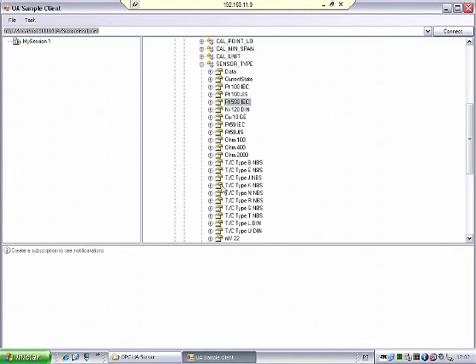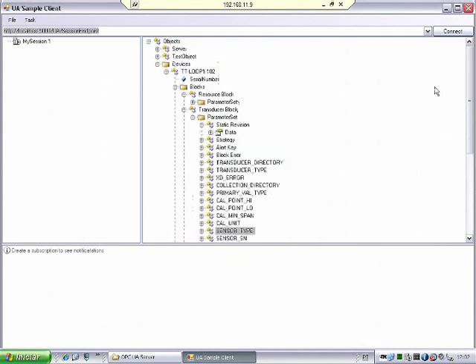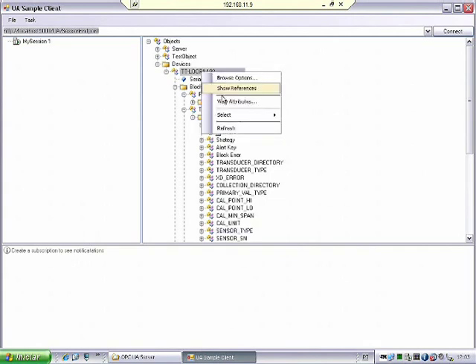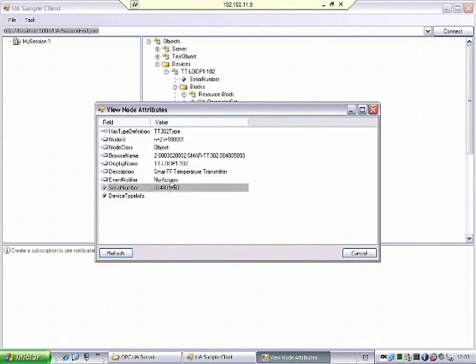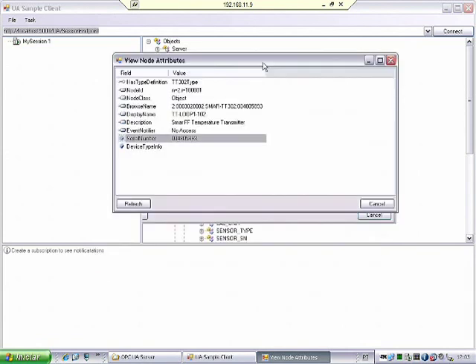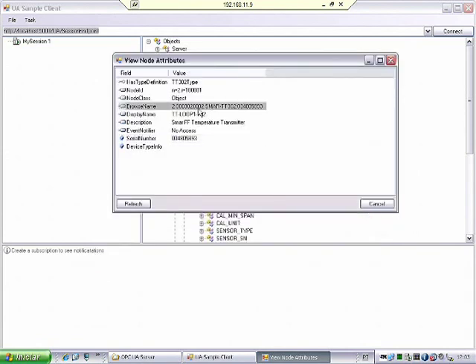I just missed the last thing here. I didn't show you the variables for the device. We have here, as shown earlier, the serial number. The information model says please supply the serial number for the client for tracking reasons or whatever you can use a serial number, for instance. And the browse name, this is not so useful, but I am just showing how the information model is going to detail every attribute that you have to fill from the ADD. The ADD says, the information model says, please put here the browse name, the device identifier. This is a unique identifier that takes into consideration the company that made the device and the device revision. And this is the tag that the network driver was able to give me from the network.